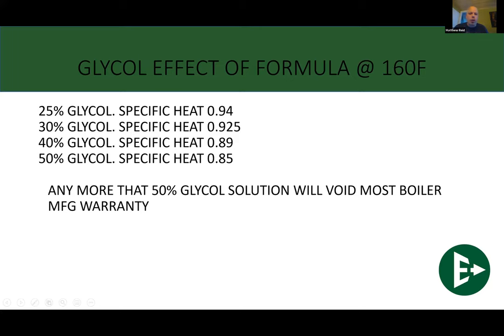Let's talk about glycol in a system here just for a second. When we're talking about efficiency drops by adding glycol, at 25% glycol, we drop our efficiency rate by 6%. At 50% glycol, we reduce our BTU capacity by 15%. Also, it should be noted, any more than 50% glycol will void most boiler manufacturers' warranties. In fact, I've yet to come across a boiler manufacturer that will let you put more than 50% glycol through it. If you happen to know one, throw it out there. I'm happy to do a bit of research. At least then I'd know, but I've never seen one.